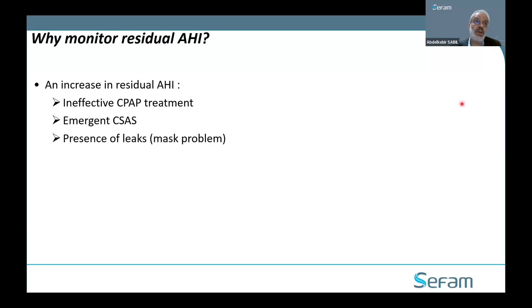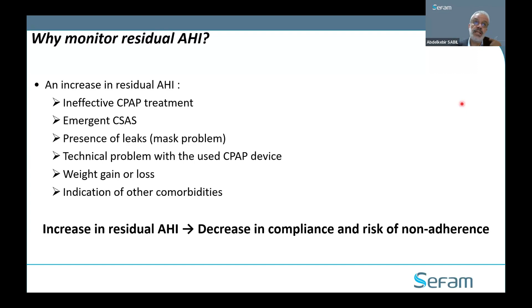That could be a technical problem. It's an electromechanical device, so there could be something with it. The patient dropped it on the floor, we don't know. Weight gain or weight loss: mostly when patients gain weight, we're going to see an increase in apnea-hypopnea index. It's most likely to be obstructive, because they need more pressure. And when there's a loss of weight, usually it's related to the fitting of the mask. The fitting of the mask needs to be readjusted. Indication of other comorbidities. And one thing for sure, an increased residual apnea-hypopnea index is definitely going to lead to a decrease in compliance, and that's a risk of non-adherence. Like you saw in the patient I showed you earlier, there were days where the patient did not use the machine, because if the symptoms are back, they're not getting the benefit of the treatment, and they're less likely to continue on the treatment.